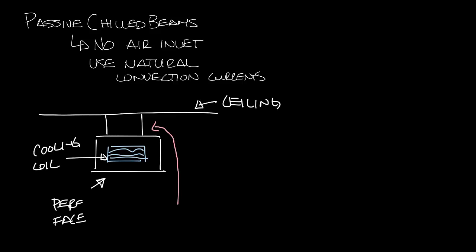So the way a passive beam works is warm air rises to the ceiling in a space. This warm air passes through the cooling coil. The cooling coil cools the air and this heavier cold air now falls into the space.